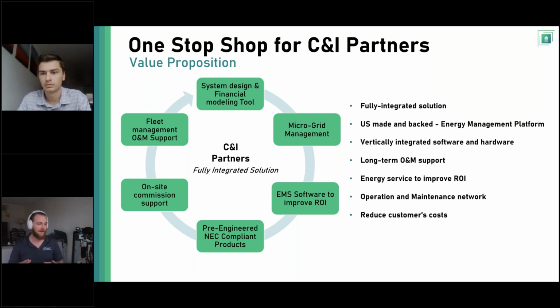Or they'll say, here's all the hardware you need to make it work—the battery, the inverter, the balance of system like grid sensing relays and islanding equipment. But then they'll say, oh, well, microgrid controls and software, EMS, energy management system software, that's not our bag—you have to go to a third-party microgrid controller to do that. That is not what we want to be. We want to be truly a one-stop shop, one hand to shake, all the corny analogies you can think of. We want to be one company under one umbrella that you can go to for your energy storage project.